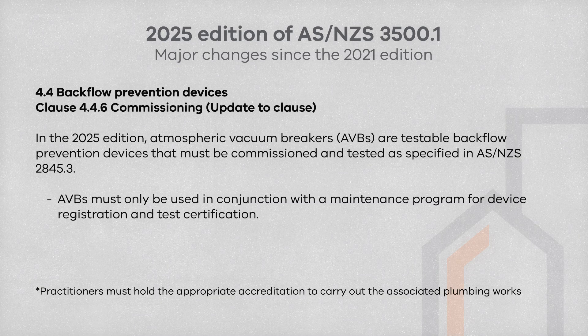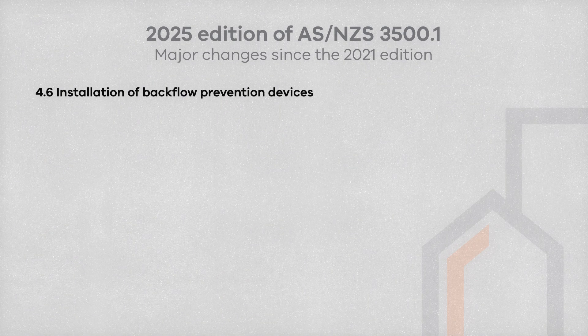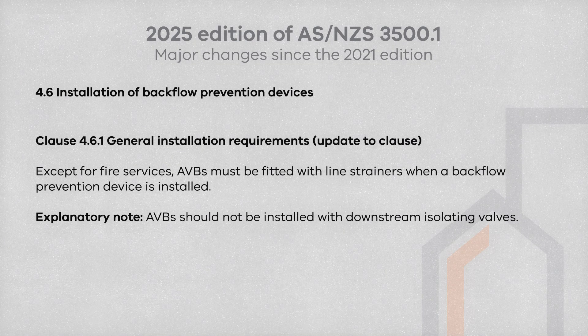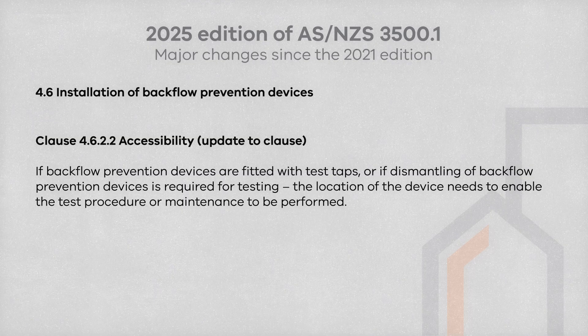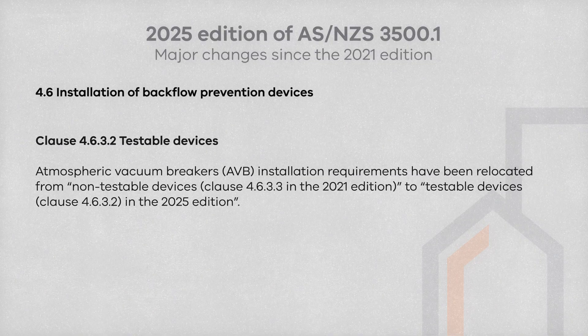AVBs should only be used where there is device registration and certification. Under Clause 4.6.1, other than for fire services, AVBs must have line strainers when a backflow prevention device is fitted, and must not be installed with downstream isolating valves. Backflow devices fitted with test taps need to ensure accessibility — as covered in Clause 4.6.2.2 — for testing purposes or where the setup requires dismantling for maintenance.